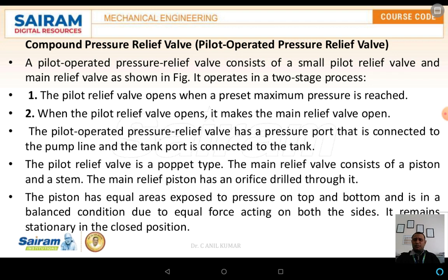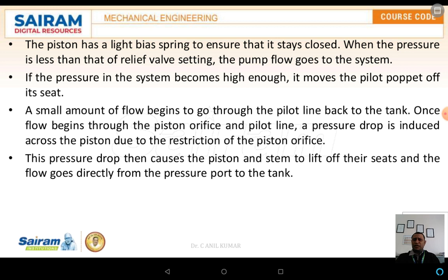The main advantage of the compound pressure relief valve is that it is operated by means of the pilot. The pilot is pressurized by means of a spring. If the pressures are small, the pilot relief valve will not be in the open position. If the pressure exceeds the limit of the pilot relief valve, the pilot relief valve automatically opens, and the oil flowing in the line passes through the main relief valve and flows into the tank.